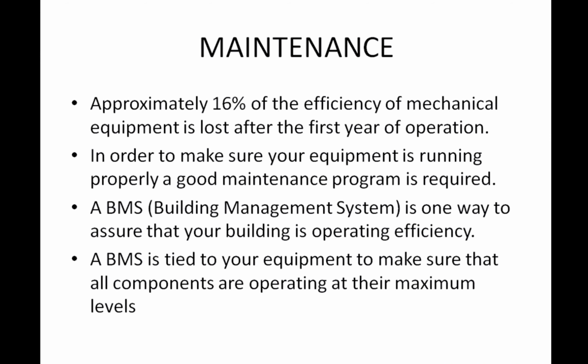All right, so just some general guidelines. New equipment will lose about 16% of its efficiency within 1 year, and that's generally due to poor maintenance or not upkeeping it. When something's nice and shiny and new and perfect, it's going to operate well. As soon as you let it go a few months and there's a buildup of dirt, debris, water, and you're not taking proper care of it, not changing out filters as frequently as they should be, you will start losing efficiency and it'll start running down.